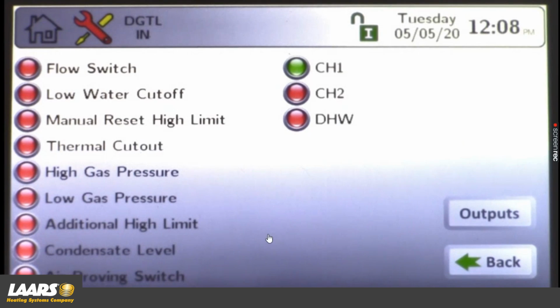This is your sequence of operation for your safety devices, such as flow switch, low water cutoff, etc. Whatever is in red, that's where you've lost power, or that's where your device is open. An example, if I make the flow switch, now everything is made, and now we're actually going into ignition or pre-purge. So again, any device that is open, in this example, I'm using a simulator, through the toggle switch for high gas pressure switch.